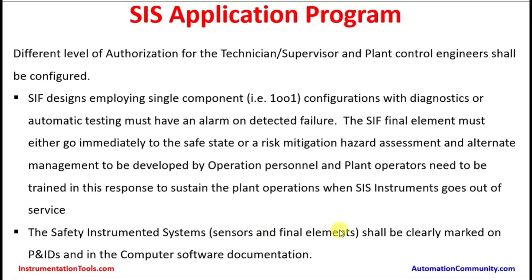The safety instrumented system sensors and elements shall be clearly marked on the P&IDs and in the computer software documentation. The piping and instrumentation diagram should have clear marking about the safety instrumented system sensors and final elements. This ensures that operations or maintenance personnel working on it will exercise caution, as they cannot simply close the isolation valves of a transmitter that is part of a safety instrumented system — because this will lead to non-sensing of the process and may create trouble for that section of the plant.